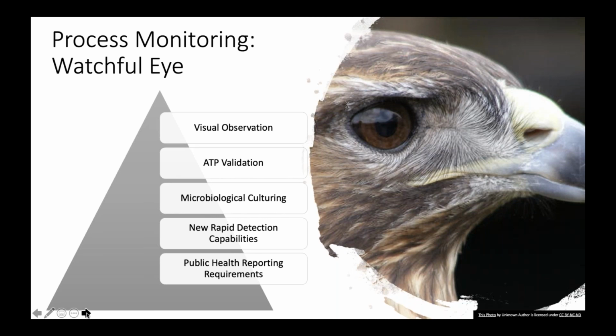ATP is a great tool, but it only measures cleanliness. It's not going to tell me anything beyond that. So if I'm looking for a good indicator following manual cleaning, then this is okay. But I will tell you, and the FDA has put out warnings about this, that using this in a larger context, we have to be very careful, because it doesn't tell me what's on there.